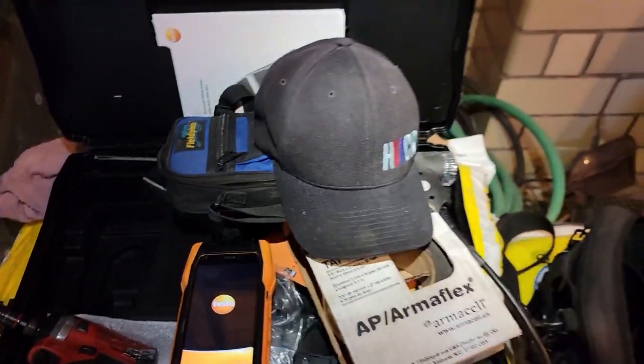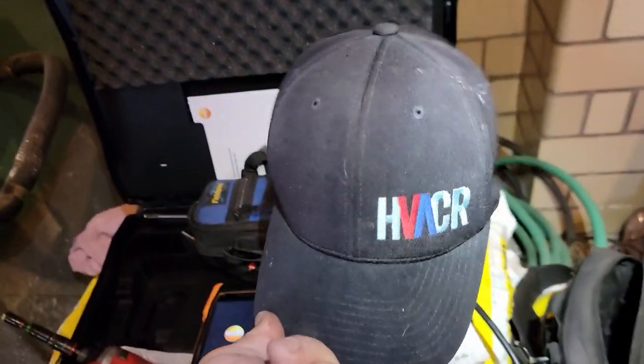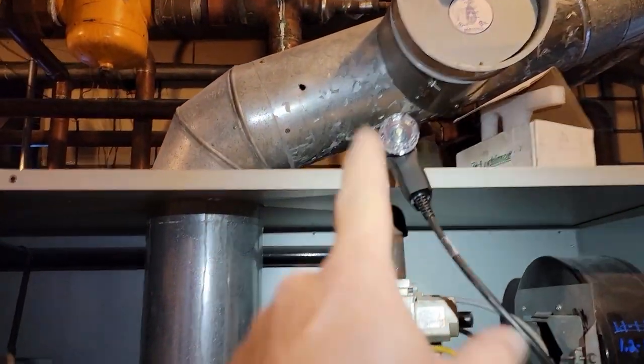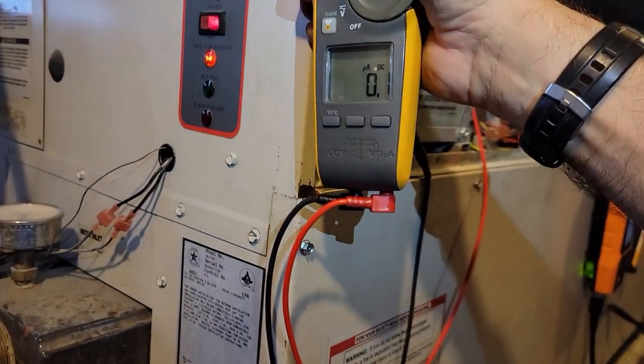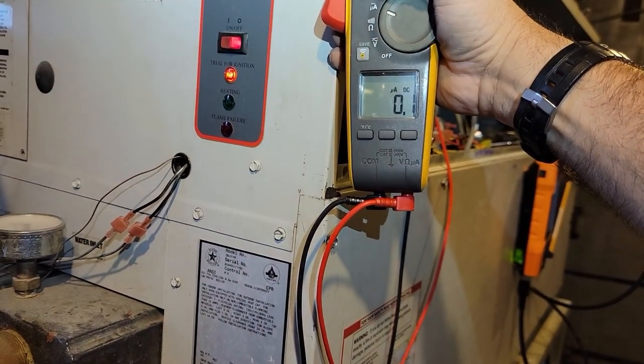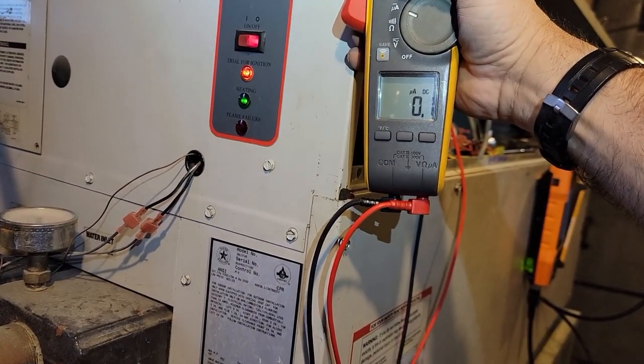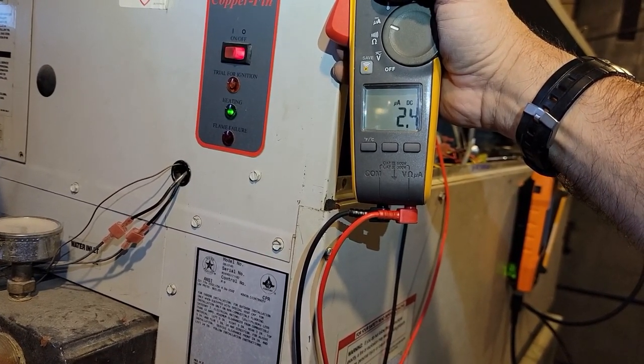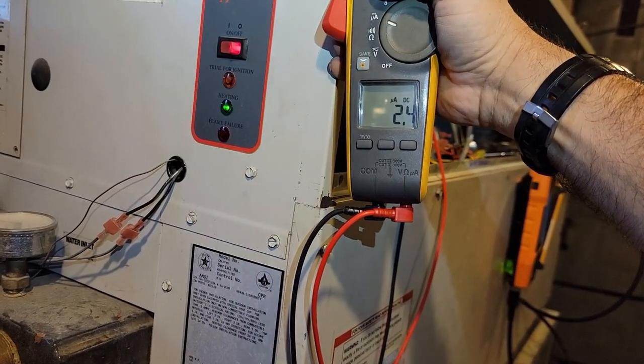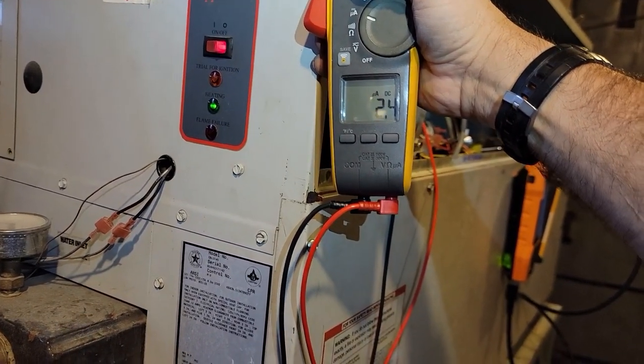One of the best hats out there, man. I've had this thing for over a year and it's held up better than all the others. Color stayed and it cleans up good. I ran it through the wash, definitely worth the money. Let's see what we get here. I'm gonna let it fire, then I'll stick it in. When it heats, that's when we're going to see the change in the microamps. Usually there's a delay after it's firing. The igniter just let off and all of a sudden boom, there goes the 2.4. So we're holding pretty good.